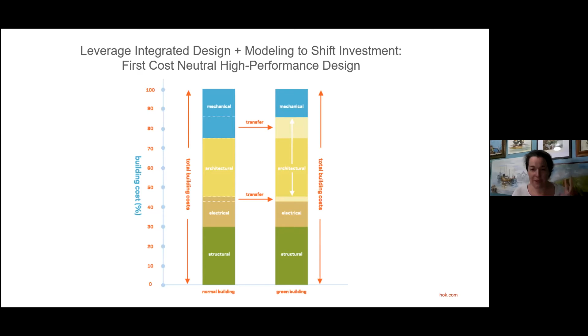This is one where we were looking at triple pane glazing for patient rooms. It certainly can improve acoustics and thermal comfort, but it also ended up eliminating the need for perimeter heat. So our long-term energy savings is great — it would have paid for itself out of those savings over time. However, by eliminating the perimeter heat system, it paid for itself immediately. So it was a cost-neutral decision that has long-term energy performance implications, and that's the kind of strategy we're looking for. That's a very quick example.